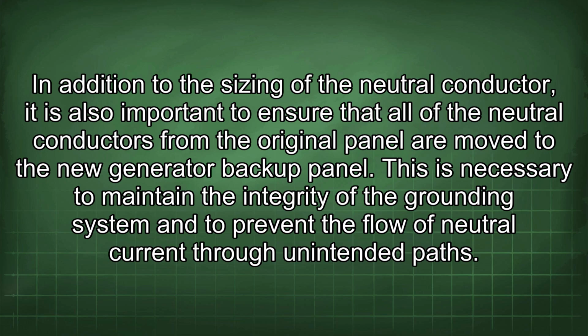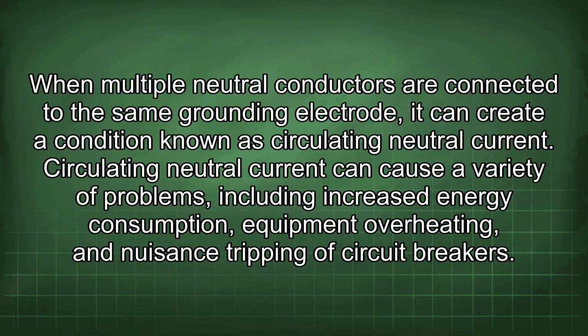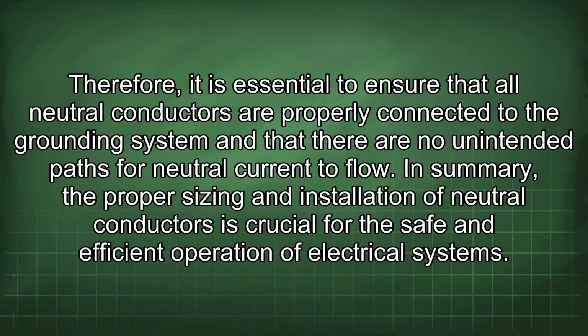unintended paths. When multiple neutral conductors are connected to the same grounding electrode, it can create a condition known as circulating neutral current. Circulating neutral current can cause a variety of problems, including increased energy consumption, equipment overheating, and nuisance tripping of circuit breakers. Therefore, it is essential to ensure that all neutral conductors are properly connected to the grounding system and that there are no unintended paths for neutral current to flow.